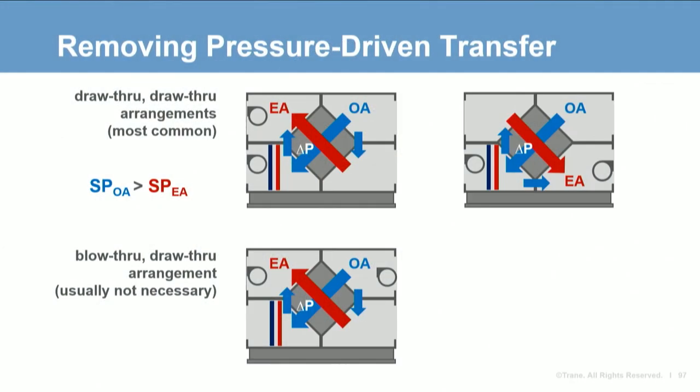To remove pressure-driven transfer, fan placement can be used to achieve the desired static pressure differential. For a cross-flow exchanger, the draw-through/draw-through arrangement will typically have a higher static pressure in the outdoor air path than the exhaust air path, removing pressure-driven transfer. If exhaust transfer is a concern, both design and expected operating conditions should be checked, and sensors can be added to measure the differential — if it goes negative, an alarm can activate or a control sequence can react. This method will result in an exhaust air transfer ratio of zero; however, the only way to guarantee no cross leakage is to isolate the exhaust.